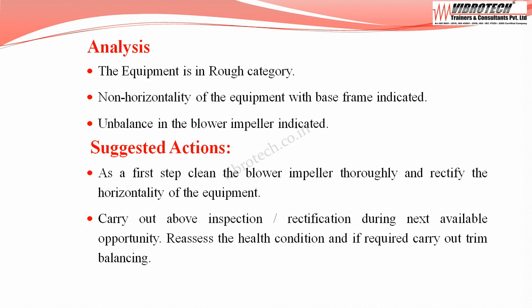Based on the analysis, the suggested corrective actions are: first, clean the blower impeller thoroughly and rectify the horizontality of the equipment. Carry out this inspection and rectification at the next available opportunity. Then reassess the health condition and, if required, carry out trim balancing.